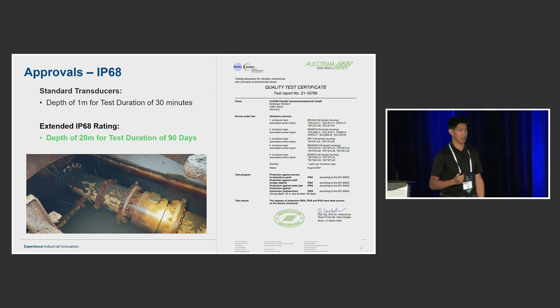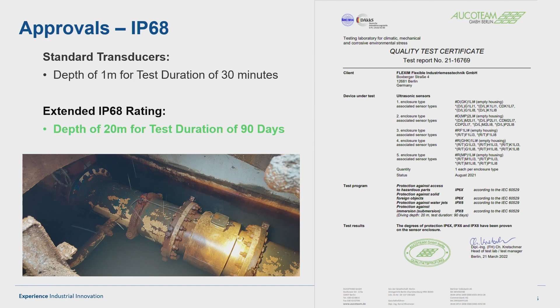Another question we get often, since you guys work in industries where flow meters can be submerged quite often, is what the IP68 rating of the transducer is. We've had extended IP68 testing where we can handle 20 meters of submergence for 90 days. That doesn't mean at 90 days the transducers just stop working, that's just the duration of the test we were able to get with IP68. We have a lot of transducers out in the field that have been submerged for years and still work, but we have to make sure we select the right options and provide a proper shield for the transducers so they'll work for those applications. We just don't have that on a certificate.